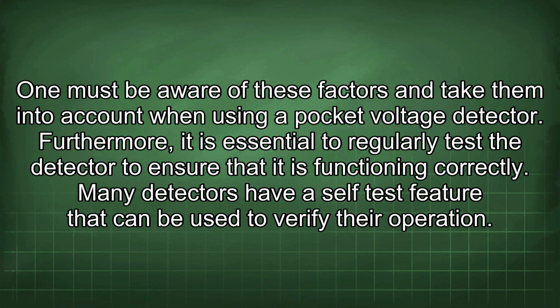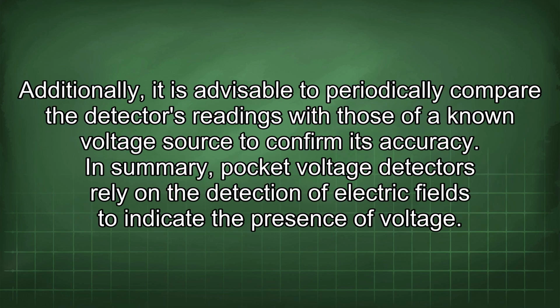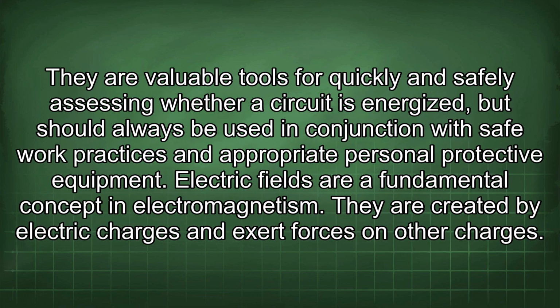Furthermore, it is essential to regularly test the detector to ensure that it is functioning correctly. Many detectors have a self-test feature that can be used to verify their operation. Additionally, it is advisable to periodically compare the detector's readings with those of a known voltage source to confirm its accuracy. In summary, pocket voltage detectors rely on the detection of electric fields to indicate the presence of voltage. They are valuable tools for quickly and safely assessing whether a circuit is energized, but should always be used in conjunction with safe work practices and appropriate personal protective equipment.